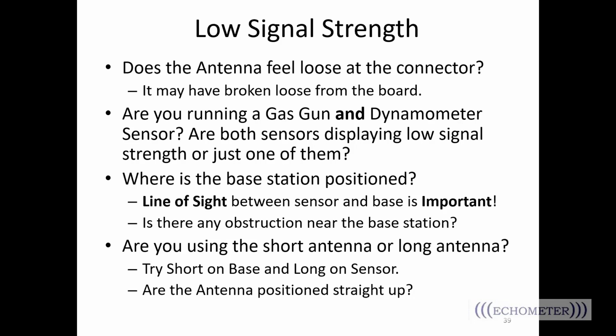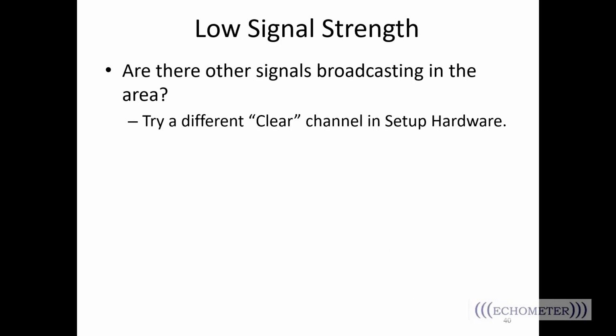Another thing you can do to troubleshoot signal strength is, are you using the short antenna or the long antenna? Try the short antenna on the base station and the long antenna on the sensor. The thought behind this is, if you have the longer antenna on the base station, then that's just amplifying the signal that the base station is able to pick up. If you have the shorter on the base station and the longer on the sensor, then you're magnifying what the sensor's sending out. That might help with some interference. And you want to make sure that your antennas are positioned straight up. Are there any other signals broadcasting in the area?